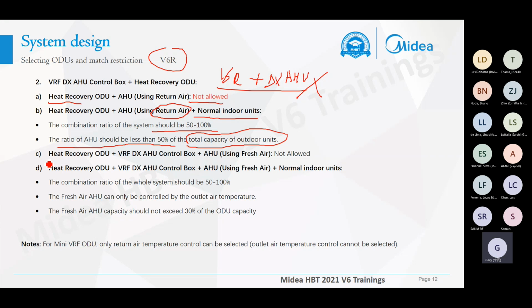This is for the return air controls. And for the fresh air control, we don't allow any directly connected AHU to the V6R. This is the same as the return air controls. One more stricter rule for the fresh air AHU connected to the V6R: the fresh air AHU capacity cannot exceed 30% of the outdoor unit capacity. And for the mini VRF outdoor units, only the return air temperature control can be selected. It means when you connect the DX AHU to the mini VRF, you cannot use the fresh air control mode.